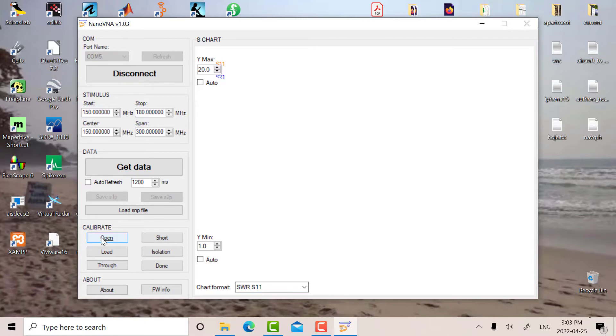So the next one is short, so I'll put the short termination on there on port 1. Okay, so the short's on there, I'll hit short, the blue bar goes across the top, so we're ready there.